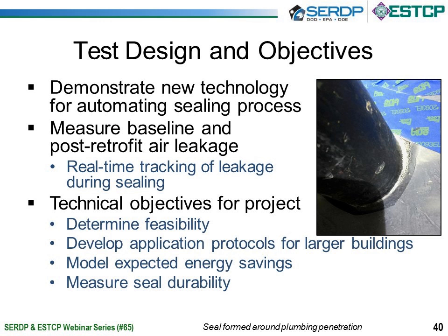So for this project, we wanted to demonstrate the new technology for automating the sealing process. Basically, we measured the baseline leakage of the building using standard blower door techniques. We performed the retrofit, and then we did a post-retrofit air leakage test, and that's the primary result for all of these demonstrations. But one of the unique things about this technology is you're able to track the leakage of the building in real time. I'm going to go over how we do that in a minute when I talk about the technology. So that has an additional benefit.